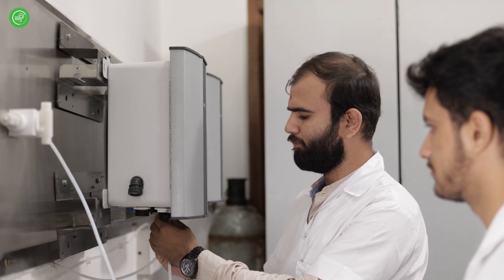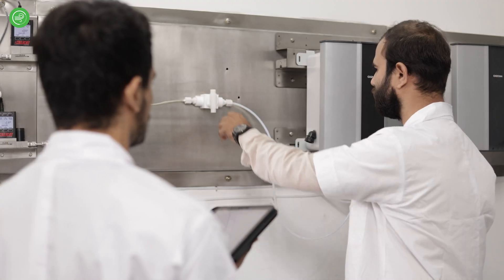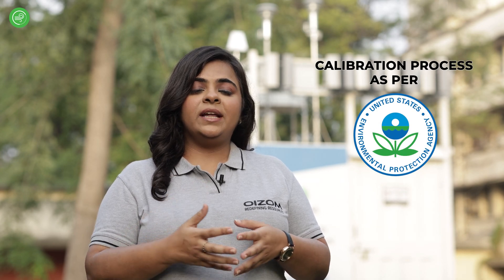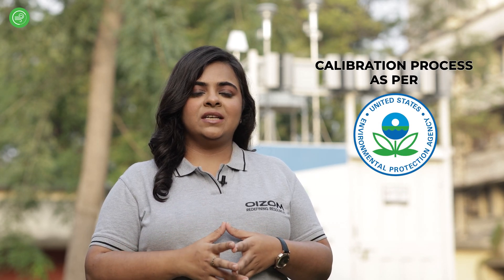The accuracy of sensor readings over the long term depends upon the sensors being calibrated both before and after the equipment is installed. For this reason, all devices at OIZOM undergo a thorough calibration process as per international guidelines by US EPA and European Technical Specifications 17660.